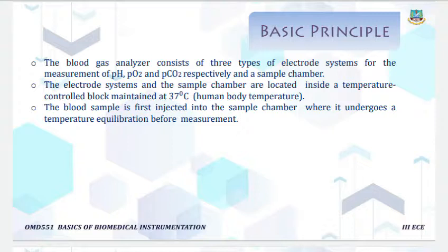The blood sample is first injected into the sample chamber, where it undergoes temperature equilibrium before measurement.